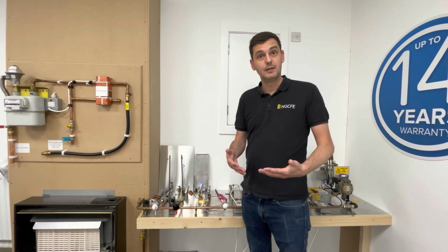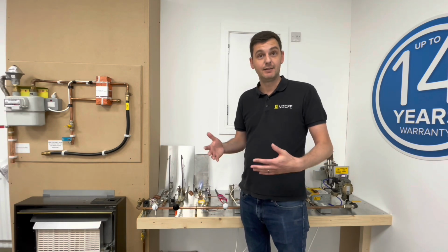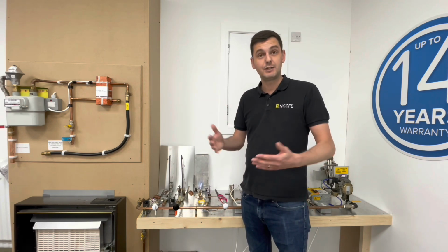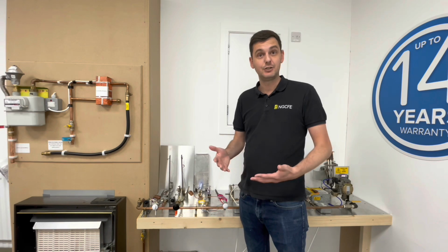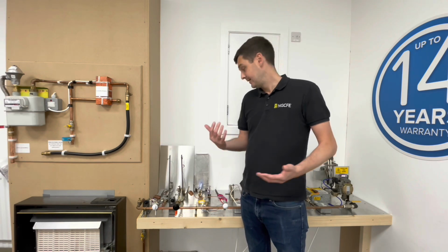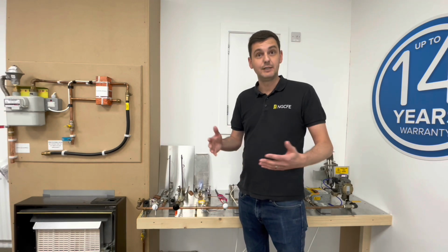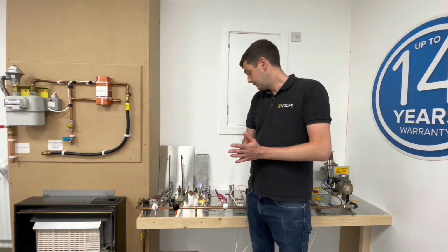So for example, this is something you might want to look at if you go out and you see boilers in the field. You could notice that somebody's bridged it out, in which case that would be another ID situation, because it's a safety device that's been manually bridged or overridden by somebody. So it's also RIDDOR reportable. So yeah, that's the interruptible thermoelectric valve.